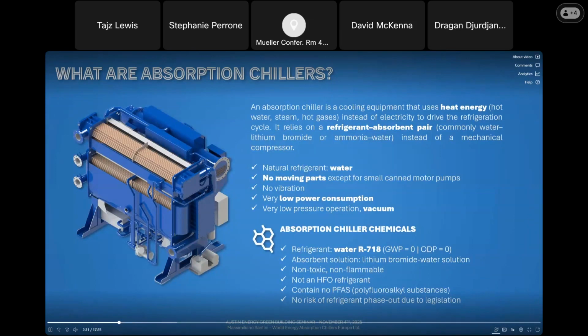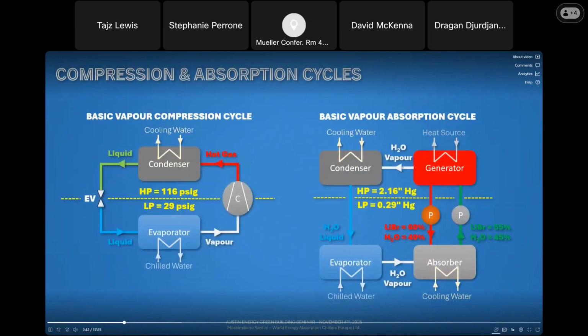The refrigerant contains no PFAS, and most importantly, there is no risk of refrigerant phase out due to legislation. Here we can see the main difference between a traditional vapor compression cycle and an absorption cycle. The main difference is in the way we transport the refrigerant vapor from the evaporator to the condenser.